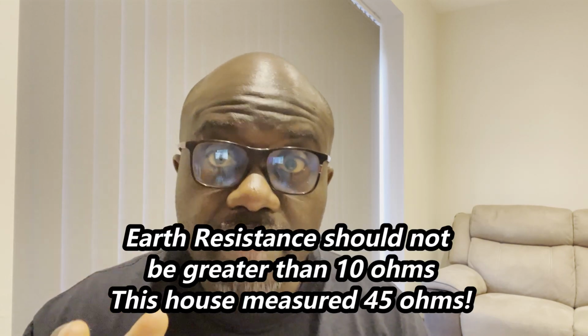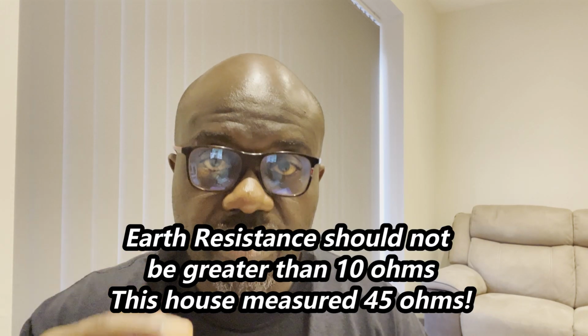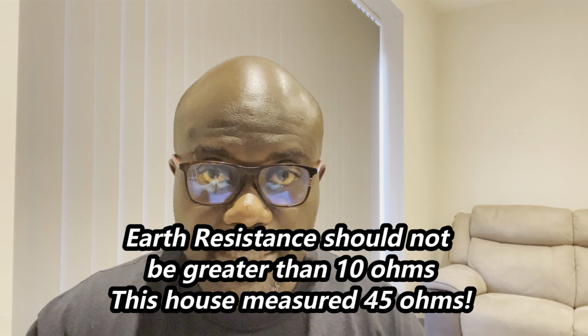So as part of this inspection of why the electrical meter is reading too high and the current flowing where it shouldn't flow, we decided to do an earth resistance test. So we did an earth resistance test in the home, and that is where you measure the resistance of the earth rod and cable to earth. And for a compliant installation, if the result is anything up to 10 ohms, generally we can accept it. If the resistance to earth is anything up to 10 ohms, we can accept it.